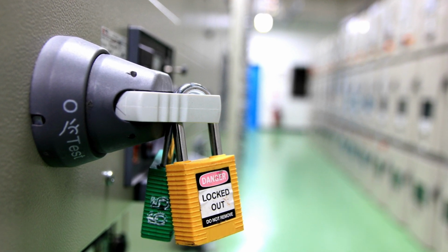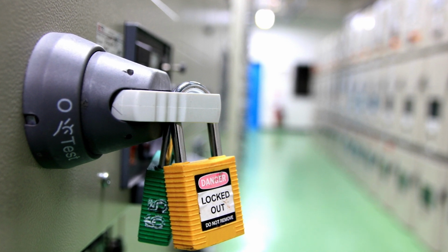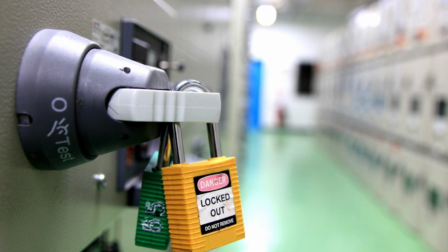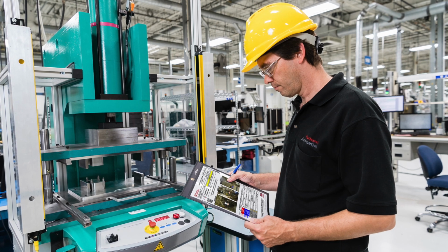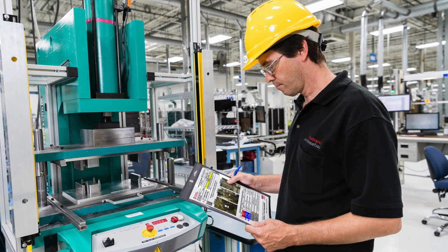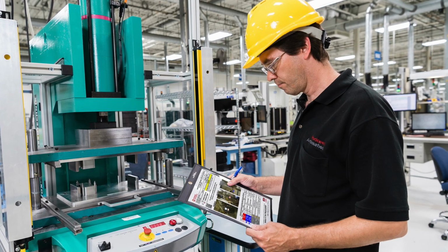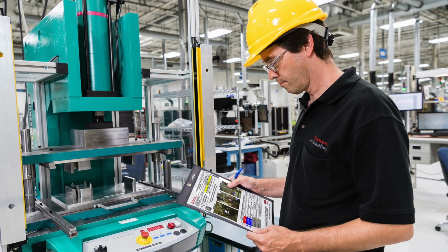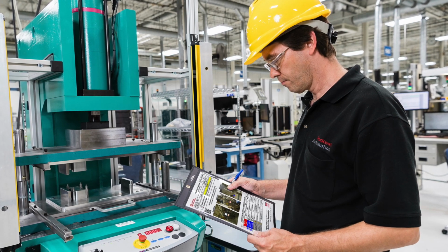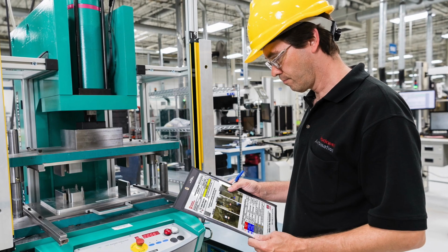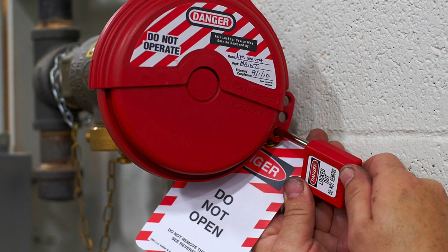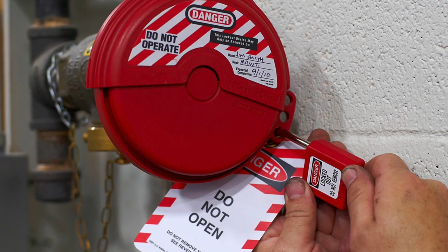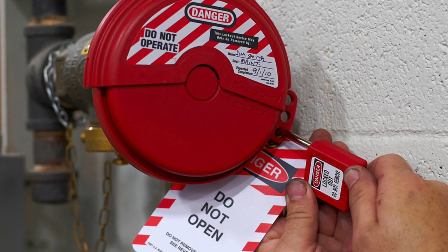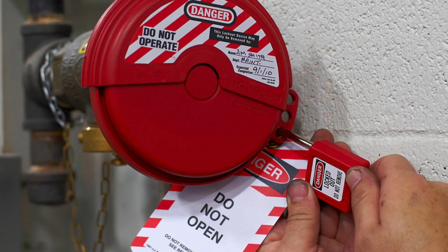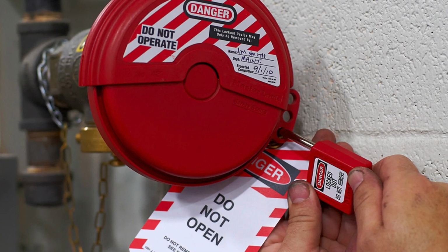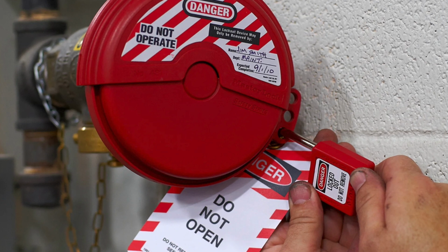Other people who work with or around the machines and equipment that are serviced in lockout tagout situations are designated as affected employees, since they may be affected by the work that is being done. These employees need to understand the purpose of your facility's energy control procedure and how it is used, and they are informed whenever lockout tagout work is being done in their work area. Affected employees are not, however, permitted to restart or re-energize a machine once it has been locked out.